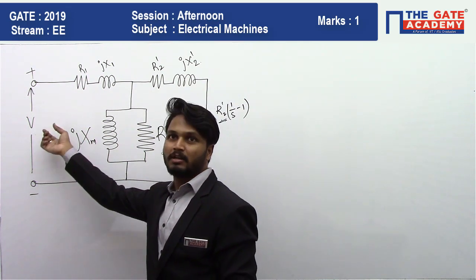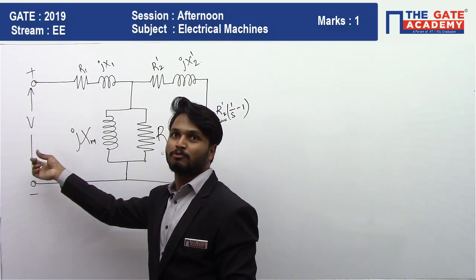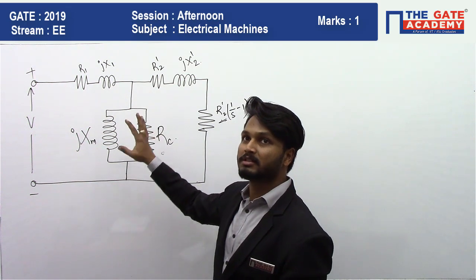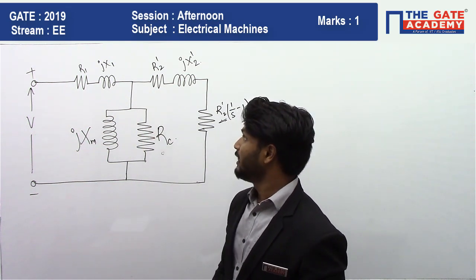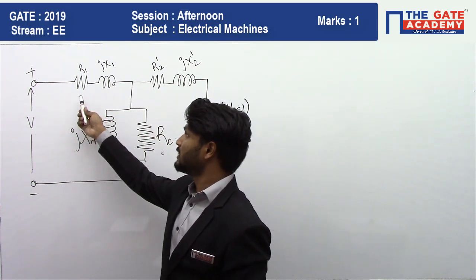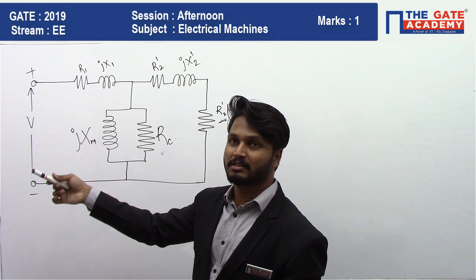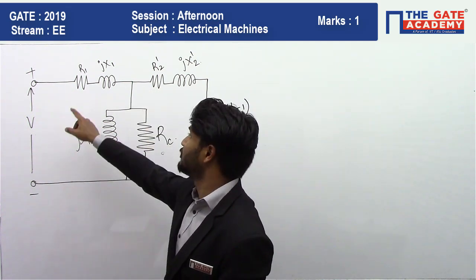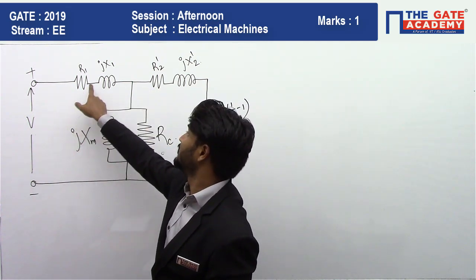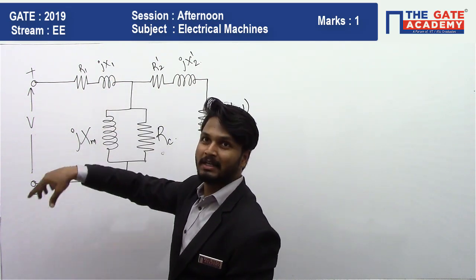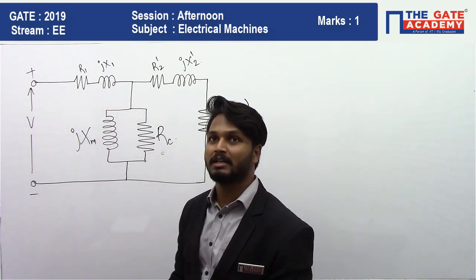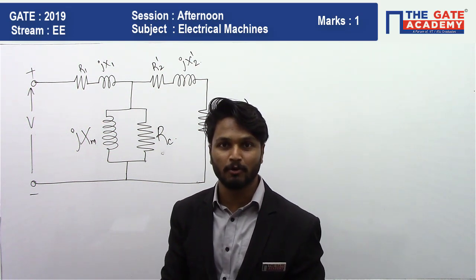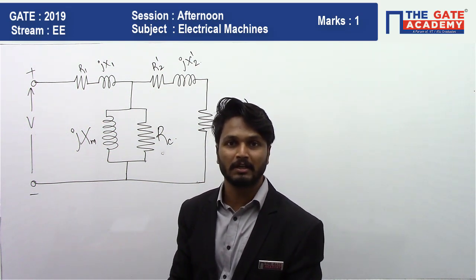If we increase or decrease the voltage, only the current through these elements changes. R1, the stator winding resistance, is a physical property of the winding and does not depend on voltage. The stator leakage reactance X1 is completely dependent on frequency and the physical construction of the machine.